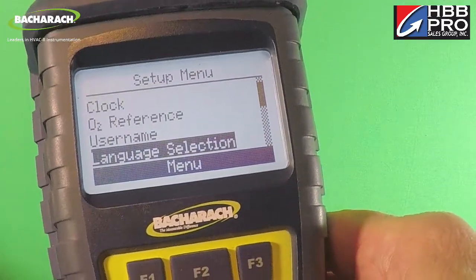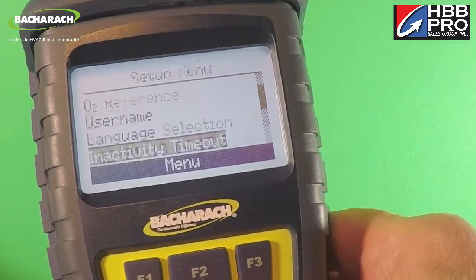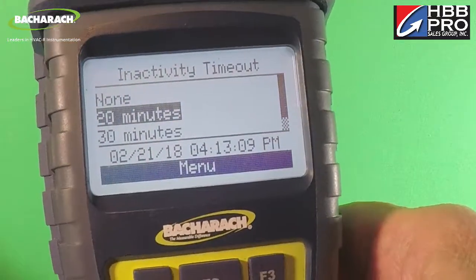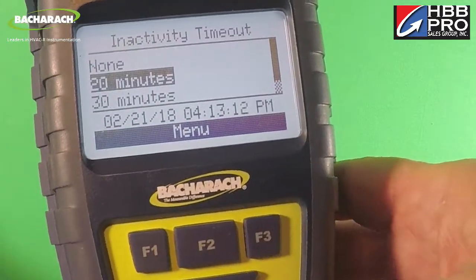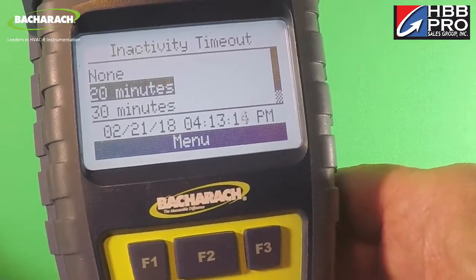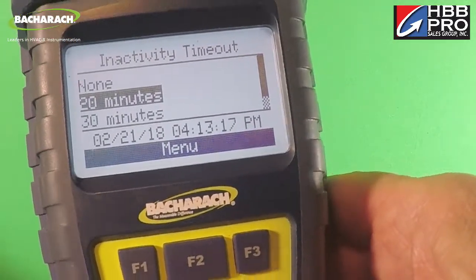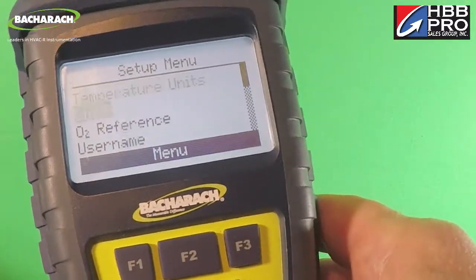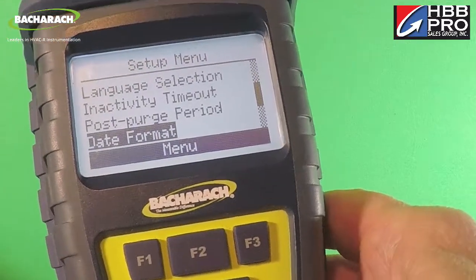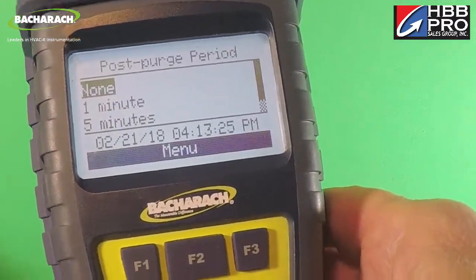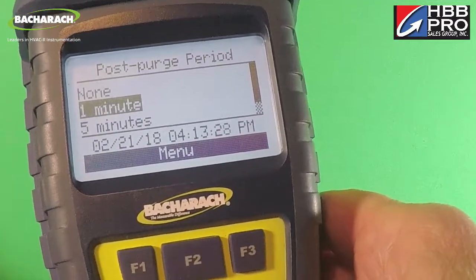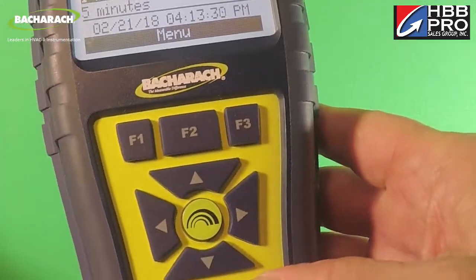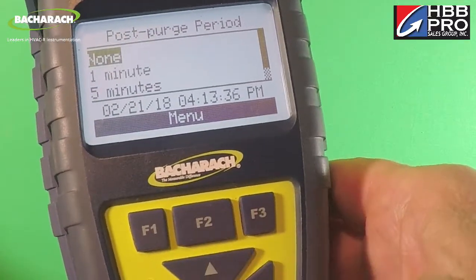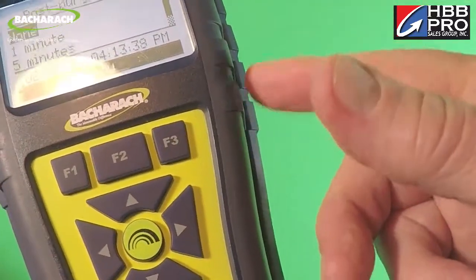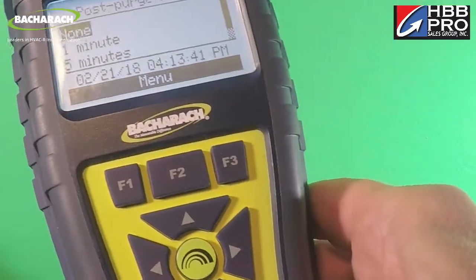Language selection, that's pretty self-explanatory. Inactivity timeout, this one's set for 20 minutes. After 20 minutes, if none of the buttons are pressed on the keypad, it'll shut the instrument off to save some battery life. Okay, go down to post-purge period. What this does is, if say I've got it set for 1 minute, when I press the on-off button to shut it off, the instrument will run for an additional minute, just to post-purge any flue gases out, try to dry any condensate out, things like that.